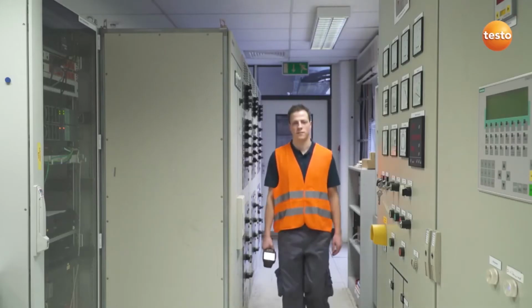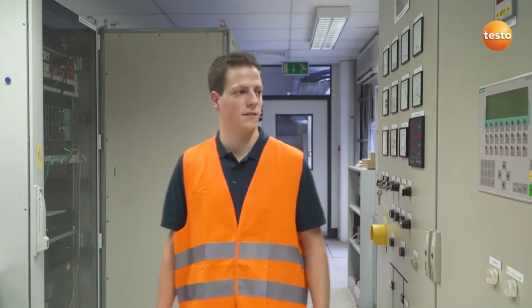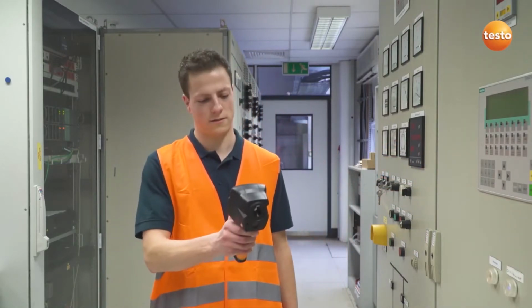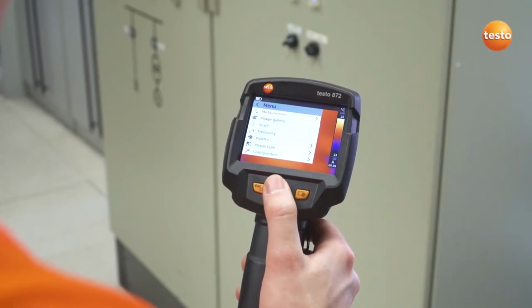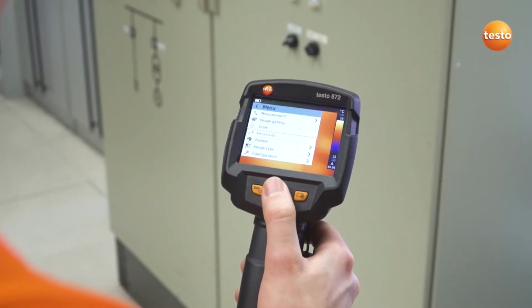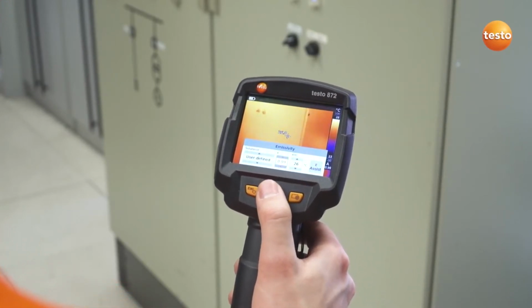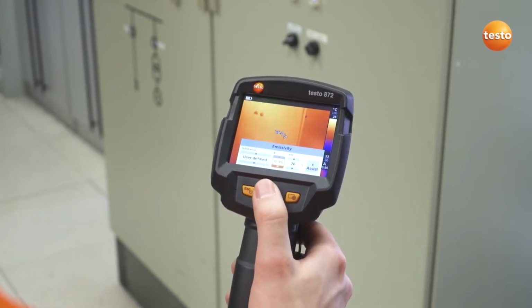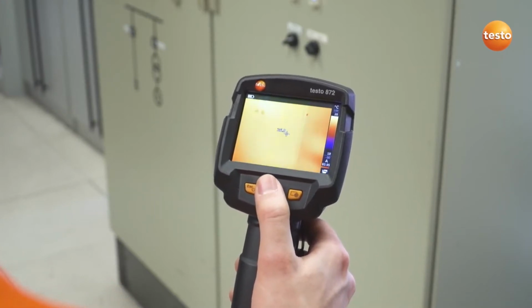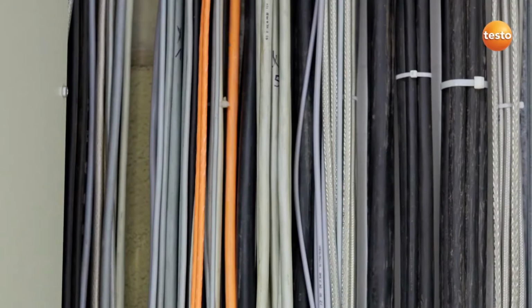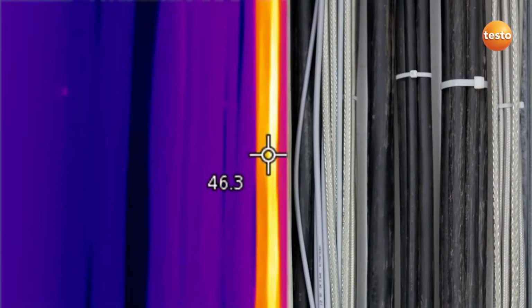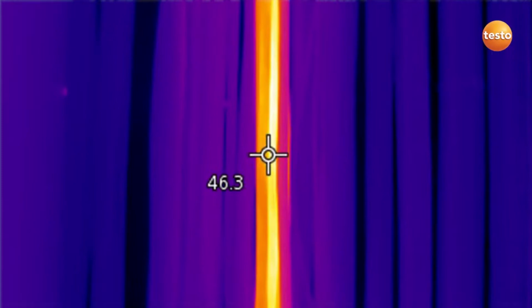We're starting the inspection with switching cabinets in this room. In addition to the ambient temperature and scale, we first have to set the emissivity of the measurement object. In this case, an emissivity of 0.95 is recommended. However, before we concern ourselves with fuses and circuit breakers, we check the wiring load on this cable here.